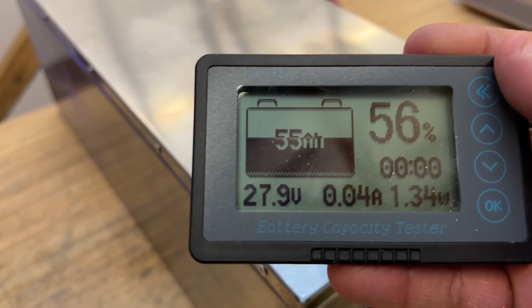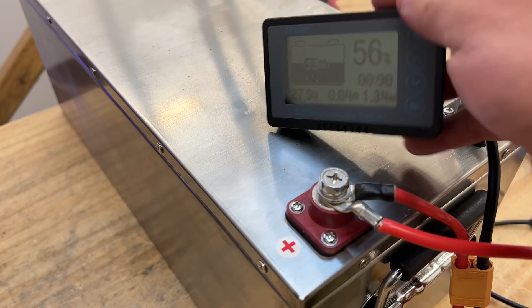All right, so it stopped discharging, and I think the reason it's at 56% - only half the battery - is that it overheated. I'm pushing this battery really hard at 100 amps, which is the max it could do. I didn't pay close attention to the meter, but the current might have been climbing, pulling more than 100 amps, and that's probably why the BMS stopped.